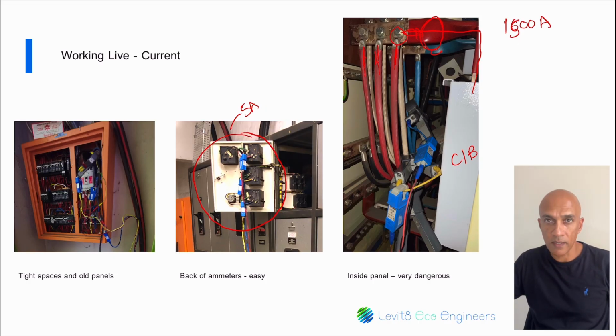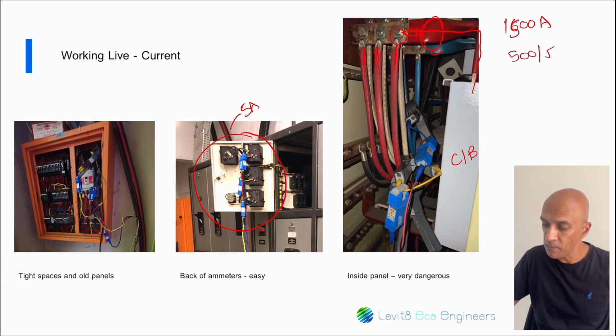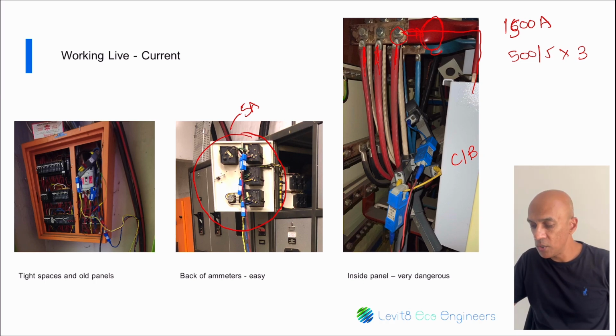So what happens here is, let's assume that each of these cables are exactly the same size. So we can connect to one of these cables and we can use a ratio of 500 to 5 amps, and then we multiply that by 3. So our end result, when we get our data, we have to multiply our current by 3, or if your instrument allows you to put in the ratio, you can measure one cable but put a ratio of 1,500 to 5. Okay. Then your data will be correct.